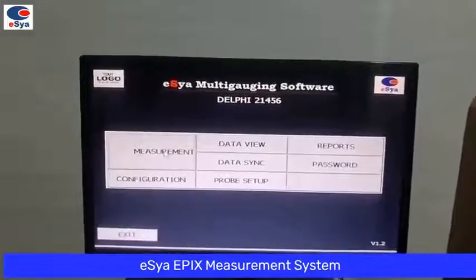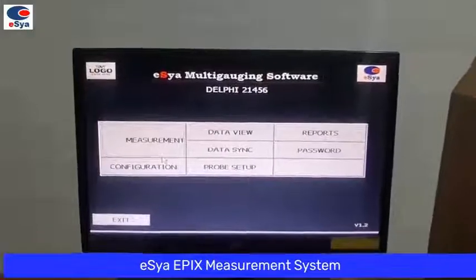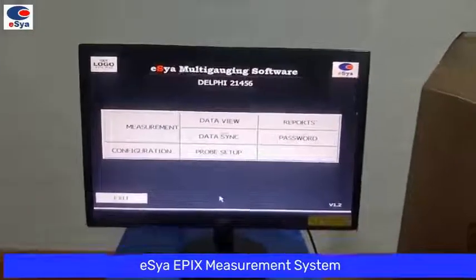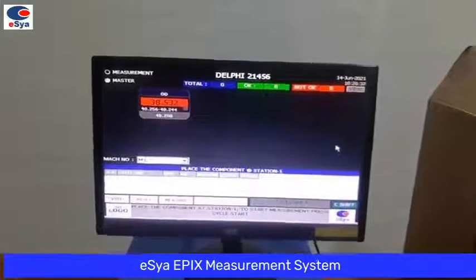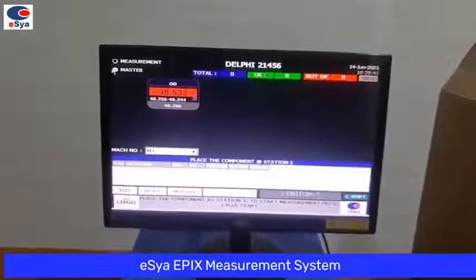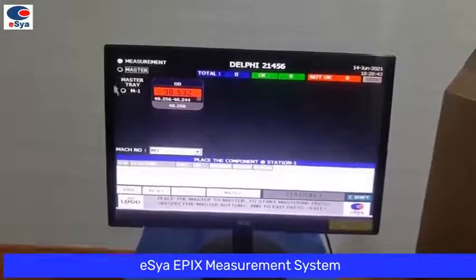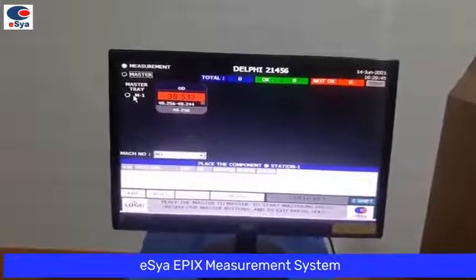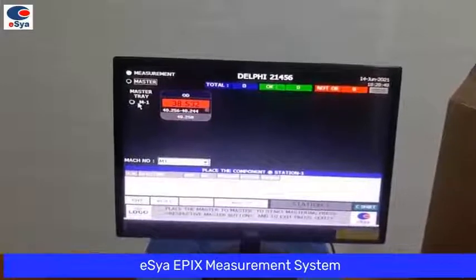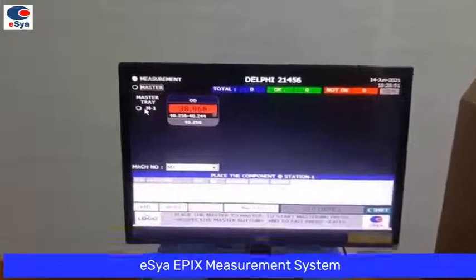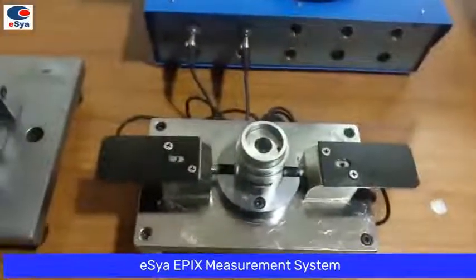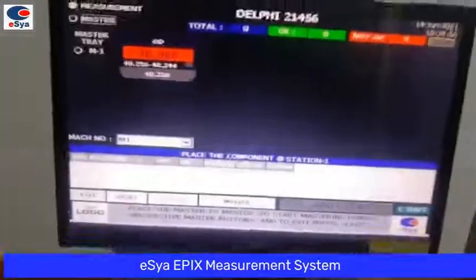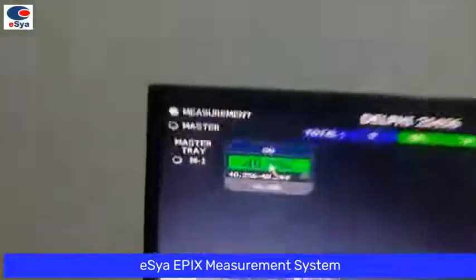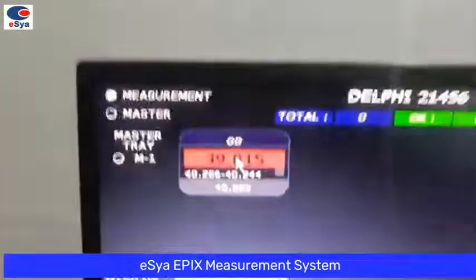Now you have to select measurement. Here you can see 2 options, measurement and mastering. In mastering mode, if multiple stations are there, it will show which station you have to master. Here we have only one station. So we have inserted the master, and now we have to press master. Mastering is done successfully. The value is showing in green mode. If I remove the master, it will show in red mode.